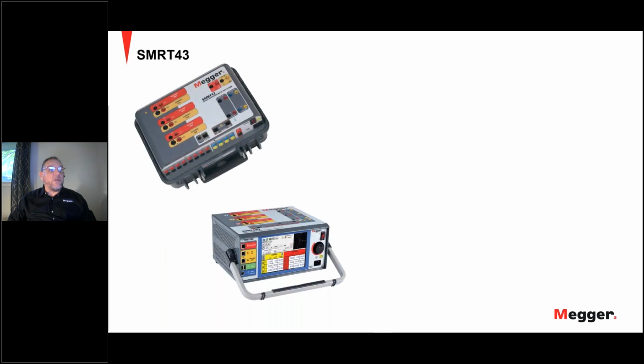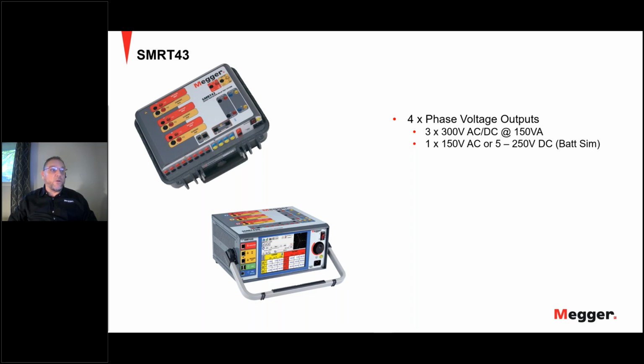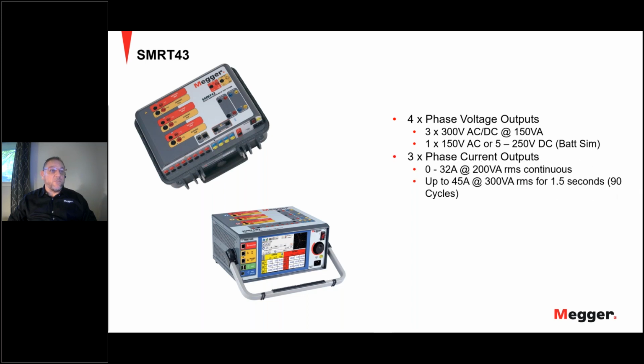So moving on to the SMRT 43, which you'll get in the standalone unit or the display unit. And again, the specifications are very similar to what you've already seen with the other units. The difference is that you've got a 4th voltage channel, which can give you 150 volt AC or 5 to 250 volt DC, which will simulate your battery simulator so you can power up the relays.